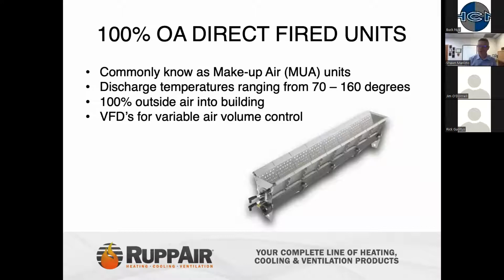Within direct fired units, we're going to talk about two primary types: 100% outside air direct fired units, and later we'll talk about recirculating style direct fired units. 100% outside air direct fired units, commonly known as makeup air units, MUAs or MAUs, are designed for replacing 100% outside air into a building that's been exhausted for some reason. Discharge temperatures on these products will range anywhere from 70 to 160. Again, 100% outside air into the building.